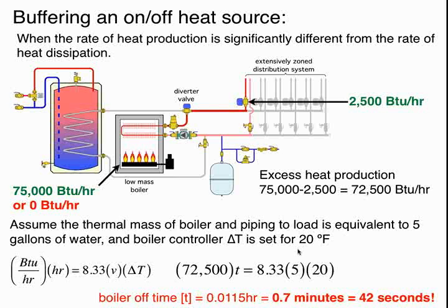Well, if we calculate how long that boiler will be able to operate when there's an excess heat production of 72,500 BTUs per hour, here's our formula: 8.33 times volume, 5 gallons of water, times a delta T of 20. You solve that, it's 42 seconds. In other words, 42 seconds of operation of that boiler would take that high limit controller up through a 20-degree swing, and it's going to shut off the burner at that point. And that would definitely constitute a short cycle.